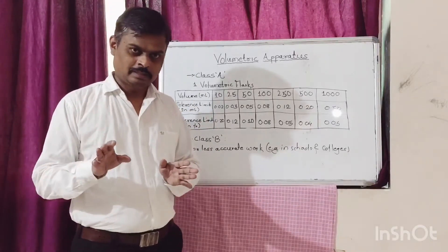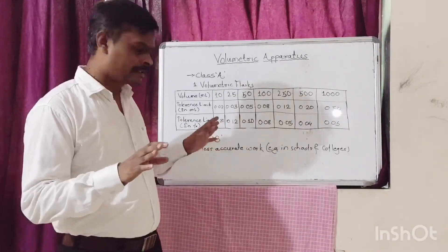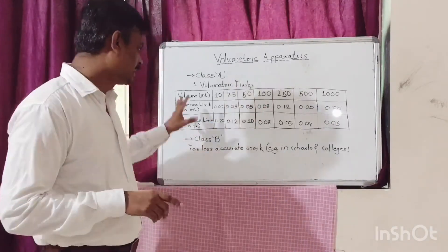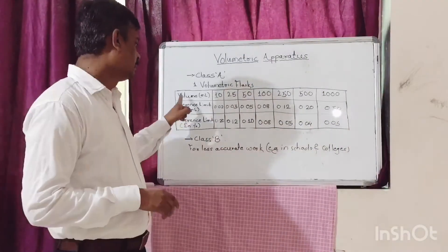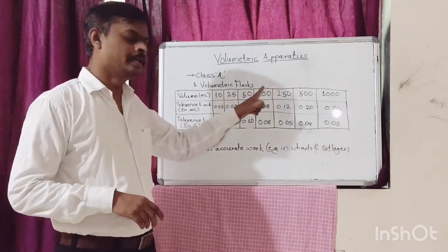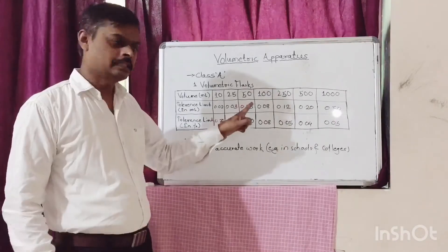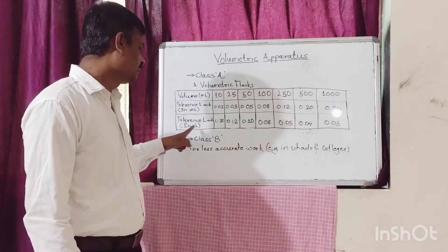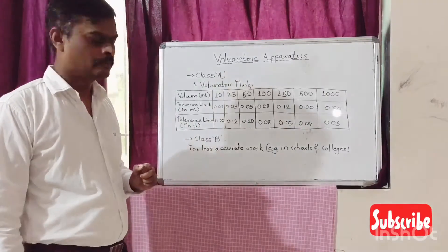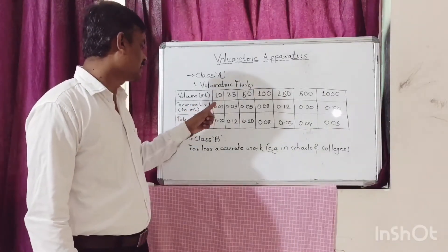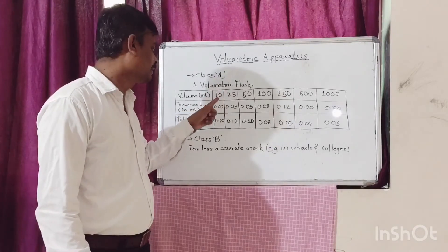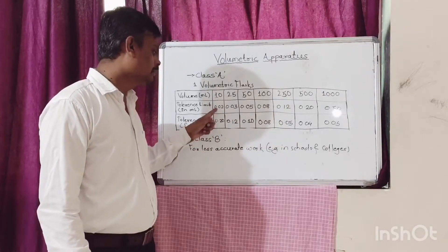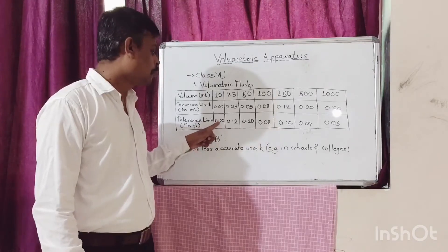For example, we have taken the tolerance limit for volumetric flasks from USP 31. This is the table for volumetric flasks. The first row contains different sizes of volumetric flasks, the second row contains the tolerance limit in ml, and the third row contains the tolerance limit in percentage. For example, for a 10 ml volumetric flask, the tolerance limit for Class A is plus or minus 0.02 ml. If you convert 0.02 ml into percentage, the tolerance limit will be 0.20%.